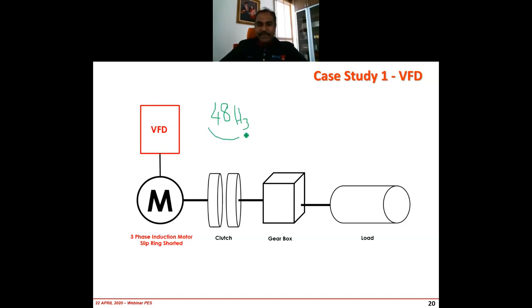And then they set the frequency to 48 hertz. Why can they not reduce more than that? Because, as I told you just now, if you reduce the speed here, you're going to give a low speed here, which is going to have an impact on the load. So what they did is they just reduced it a little bit, by 2 hertz, assuming that, okay, we can see a saving. But there is no saving at all.